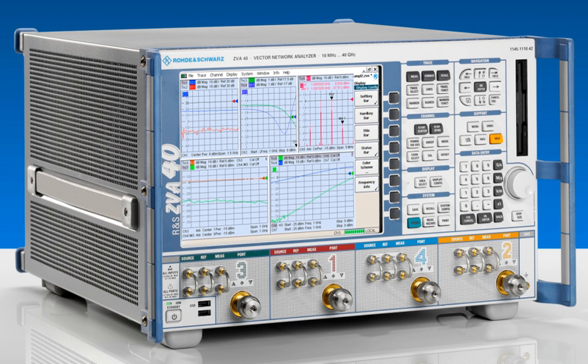Most network analyzers will have the ability to have a user-defined calibration kit. So if a user has a particular calibration kit, details of which are not in the firmware of the network analyzer, the data about the kit can be loaded into the network analyzer and so the kit used. Typically, the calibration data can be entered on the instrument front panel, as well as loaded from a medium such as floppy disk or USB stick, or down a bus such as USB or GPIB. The more expensive calibration kits will usually include a torque wrench to tighten connectors properly and a connector gauge to ensure there are no gross errors in the connectors.